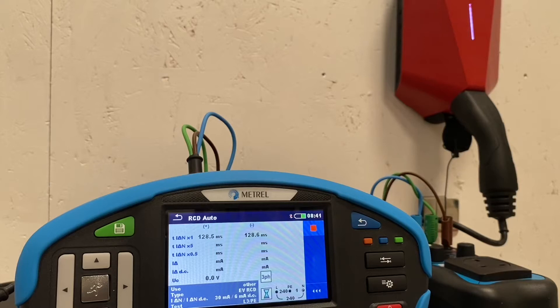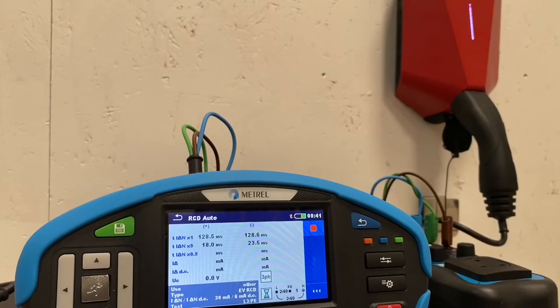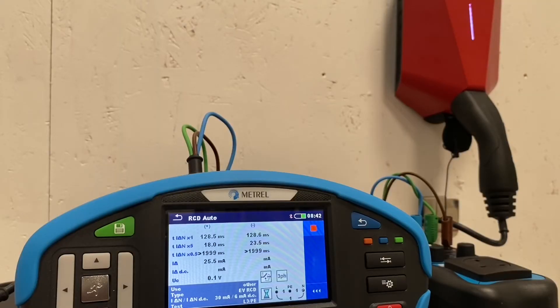The tester is clicking away in the background, bringing in the results. It's dropping out the RCD, resetting itself, and going through the test sequence. The auto function on the Metrel 3155 does this, and the Metrel 3152 would do the same. So we're going through the sequence - it's just happily doing the tests while we enjoy our coffee. We'll start to see the results coming in towards the end of the test sequence, just doing the ramp test.